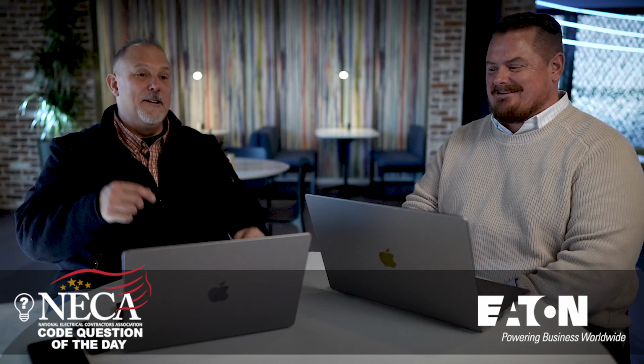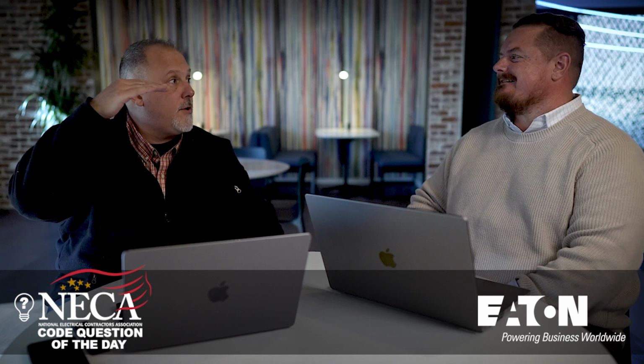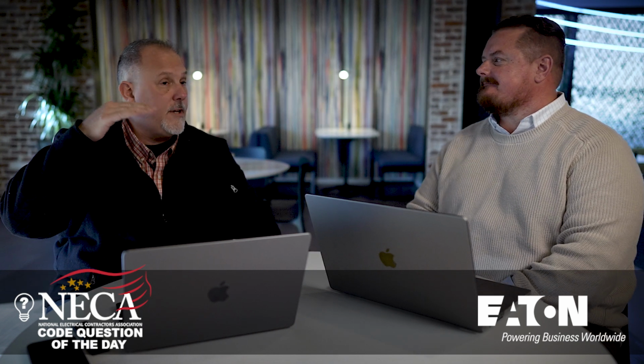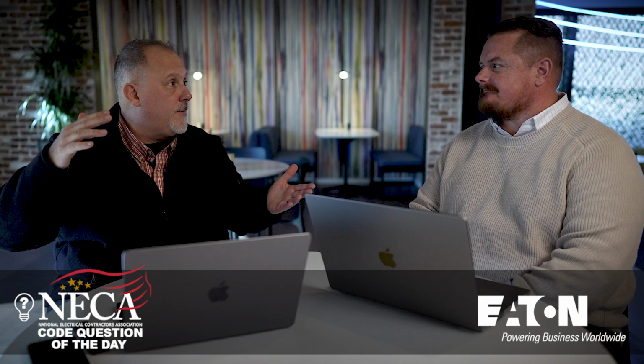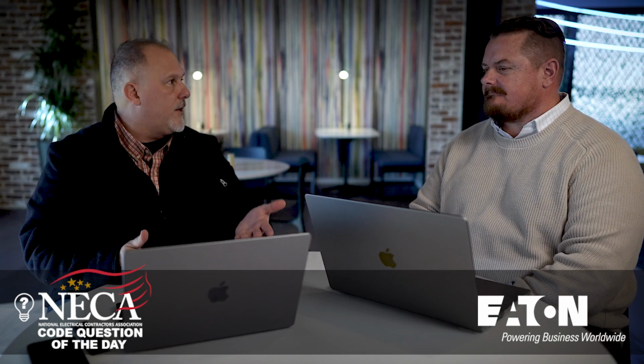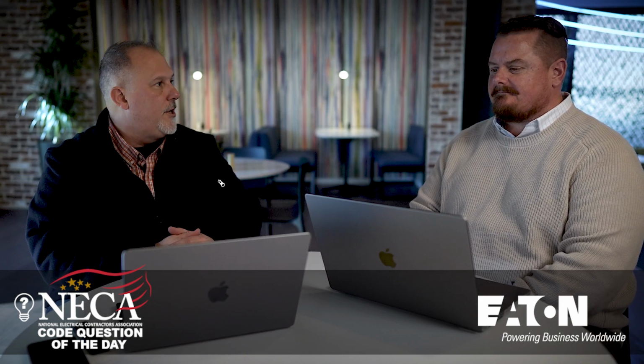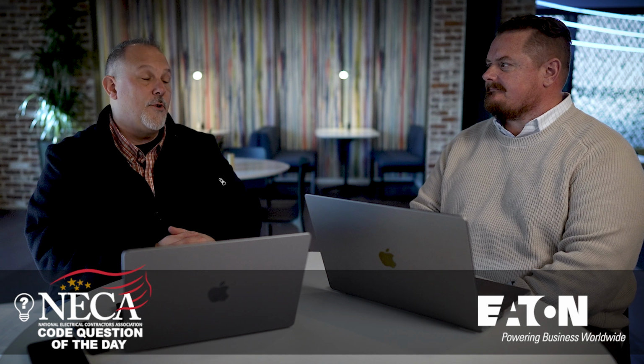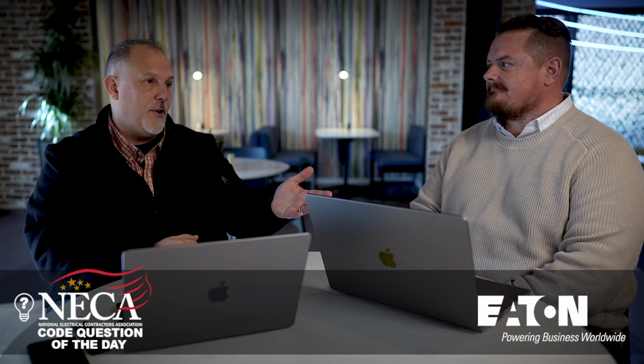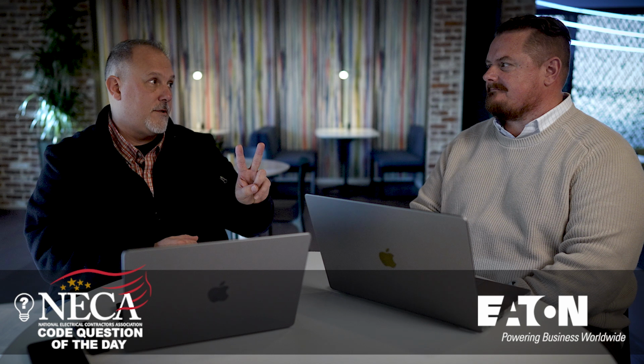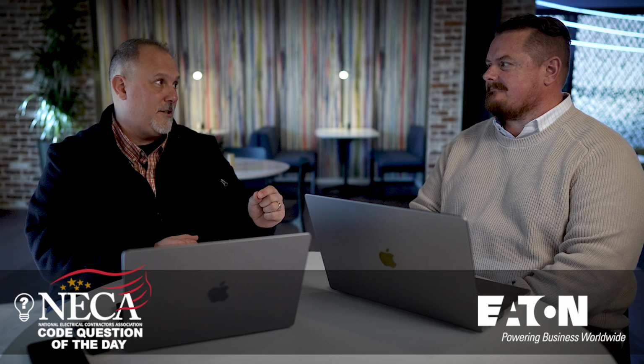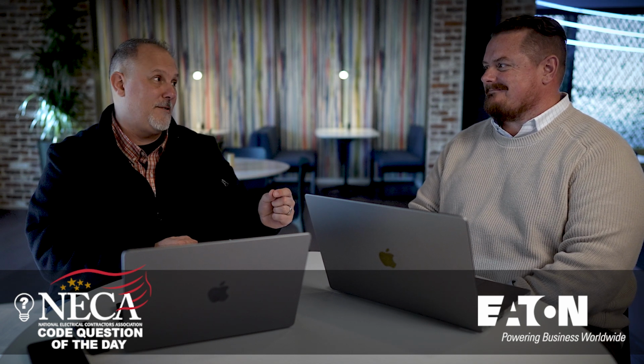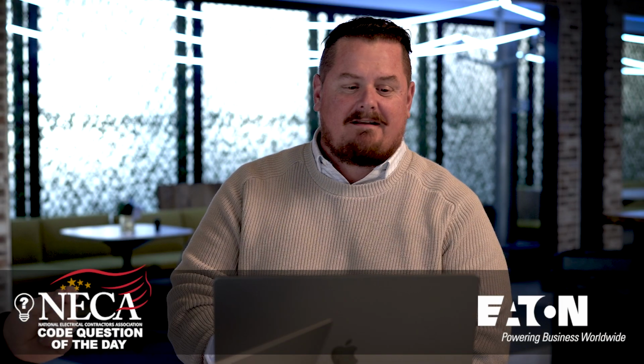That's from NEC, right? So you have a lot of fault current at the top of that building. You could have 50,000 amps, 40,000 amps, and then you've got a 5K elevator control panel. And you say, well, now what am I going to do? So, which we're going to get into. In my opinion, you've got two scenarios. One is a new installation, and there's no excuses. No. Right? No. I mean, because let's be real.